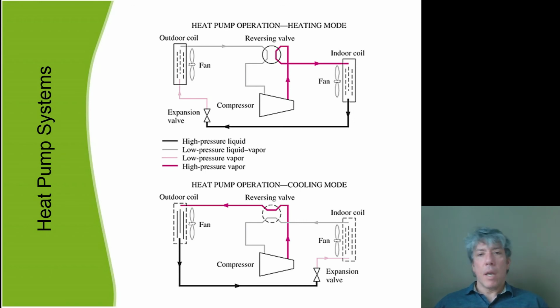Now, heat pumps are often made, in fact, I've never seen a heat pump that was not also an air conditioner, because the way you set up a heat pump is so similar, and the devices required are so similar to what's needed for an air conditioner. All you have to do is add a fairly simple device to make it both, and that device is not all that expensive. So, as I said, the heat pump I have operating has this device.